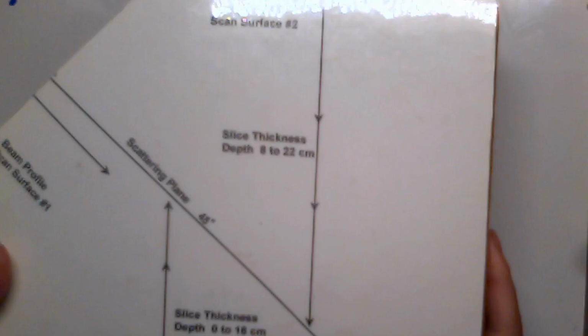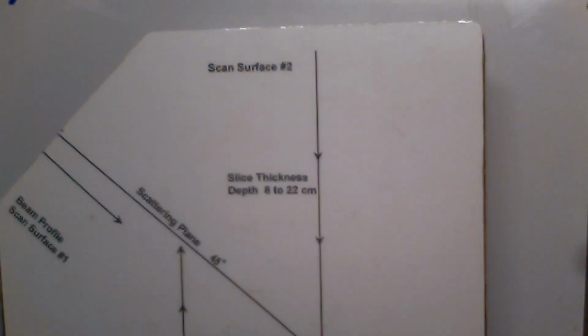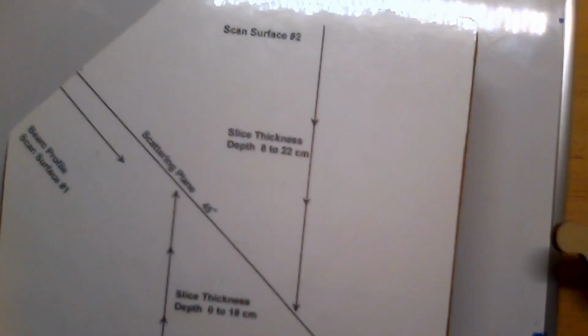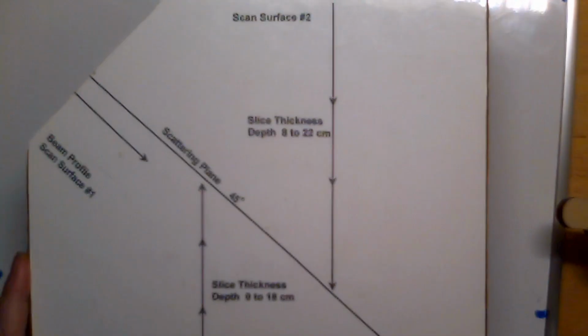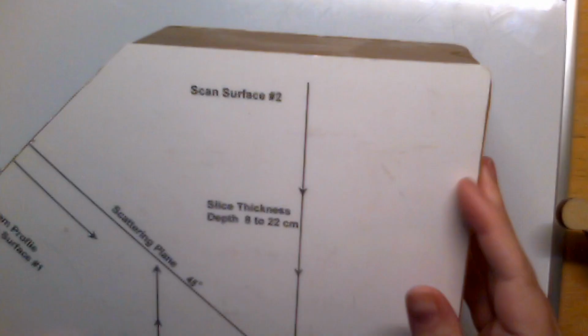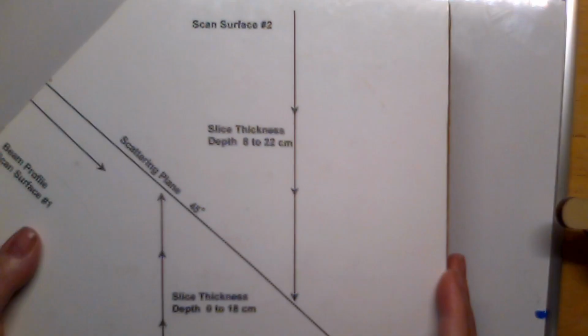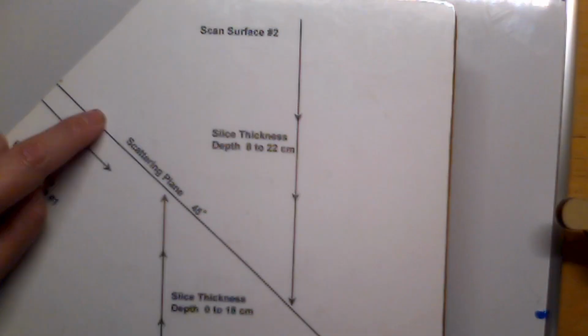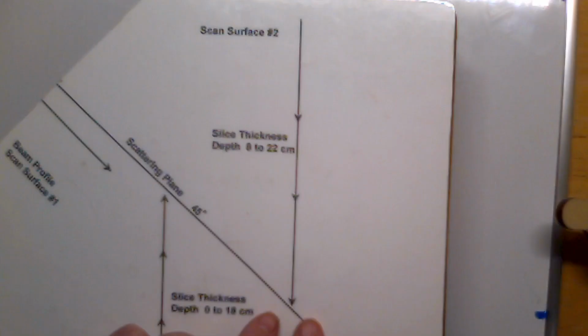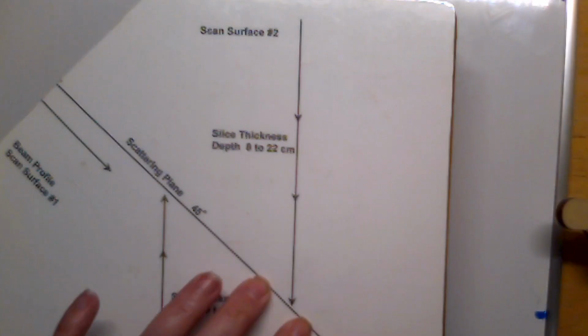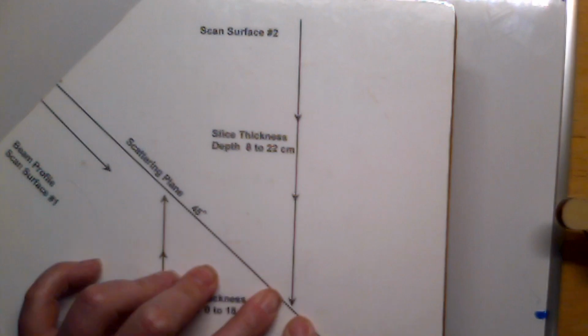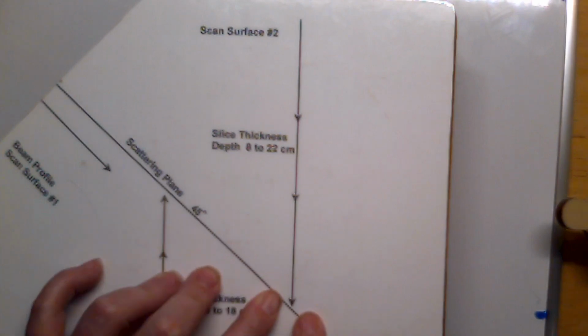I also have a slice thickness phantom. Here it is. So with the slice thickness phantom, we have the flat edge up on top here. So we would image through this edge, and as that sound beam comes down, it's going to interact with the scattering plane, or that flat bar that we talked about. And as it interacts with us, it'll tell us how much of that flat bar it can see, and that's going to tell us how wide or how tall the elevational resolution of our beam is.